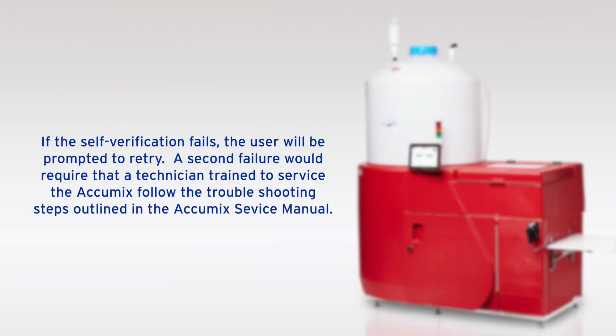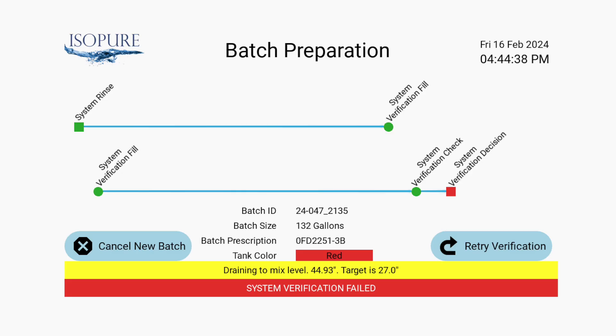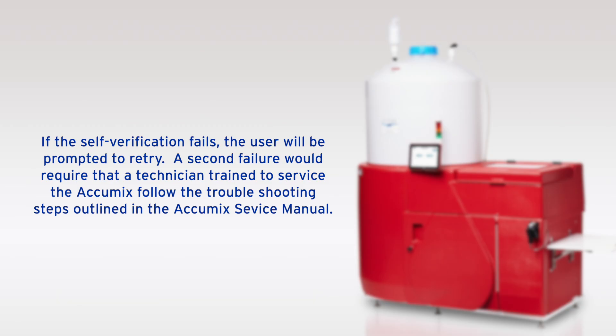If the self-verification fails, the user will be prompted to retry. A second failure would require that a technician trained to service the Accumix follow the troubleshooting steps outlined in the Accumix Service Manual. The current contents of the tank will be discarded as part of this process. Please note that you cannot begin a new batch until troubleshooting has been completed.